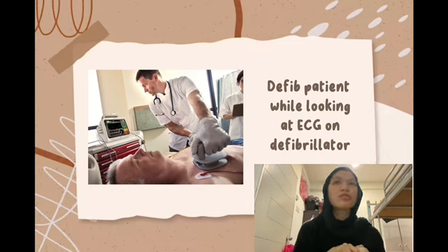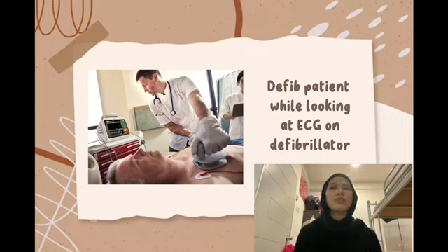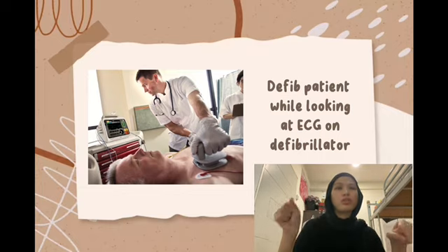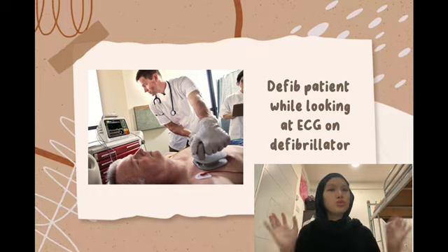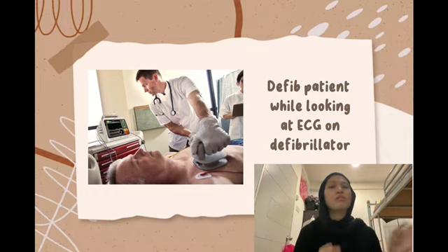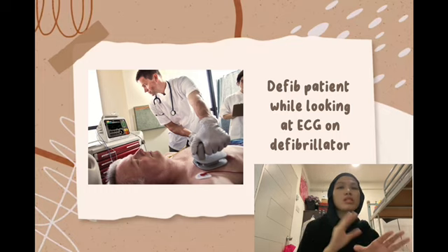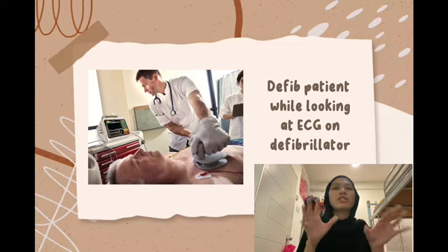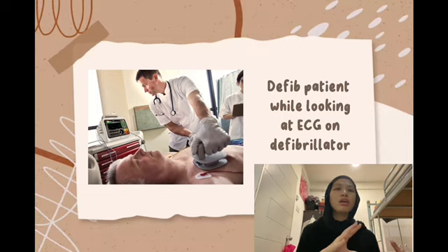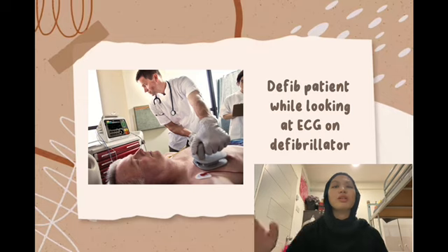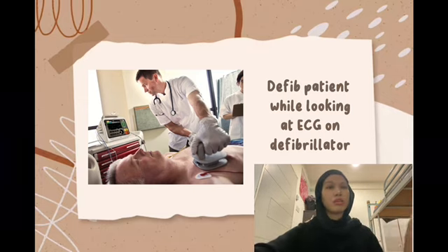Okay, so basically to ensure safety during the shock, healthcare staff should always announce the following statement. Basically, I am going to shock on 3, and then 1, I'm clear, 2, you're clear, 3, everybody is clear. So basically, why we have to announce this statement is because defibrillators pass an electric current through the patient's body, right? So thus, if anyone is touching or has any sort of physical contact with the patient at the time when the doctor administers the shock, they may also get shocked. And while shocking the patient, make sure to look at the ECG pattern at the same time on the defib machine.